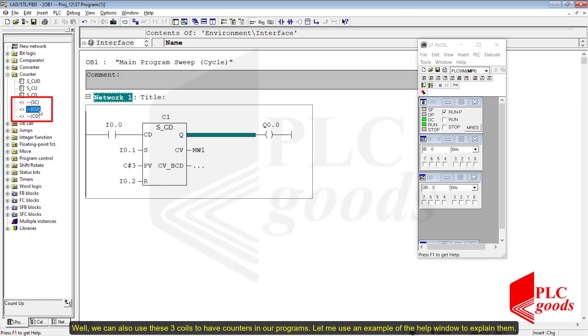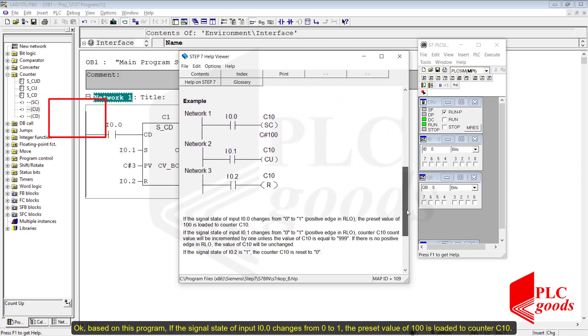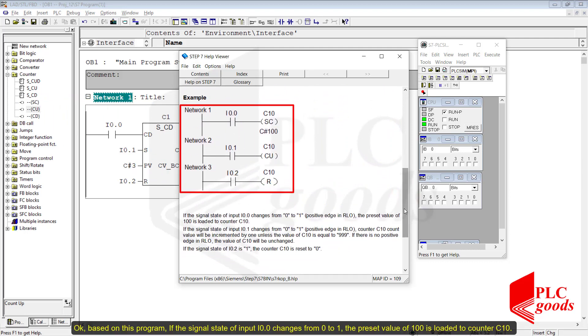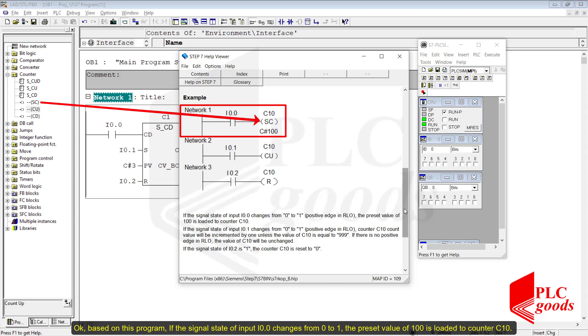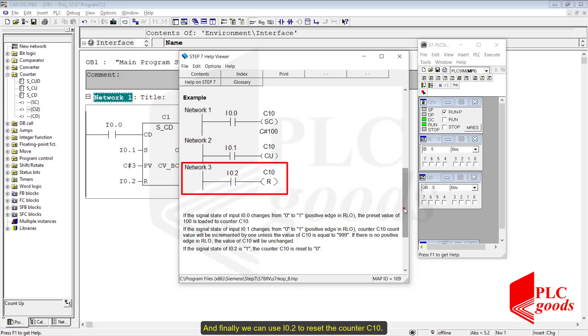We can also use coil-style calls to use counters in our programs. Based on this example from the help window: if the signal state of input I0.0 changes from 0 to 1, the preset value of 100 is loaded to counter C10. If the signal state of I0.1 changes from 0 to 1, the value of counter C10 will be incremented by 1 unless its value equals 999. We can use I0.2 to reset counter C10.